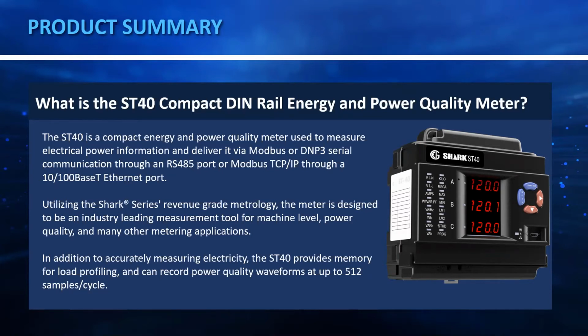This is especially important for factories or in universities where there are labs with very critical equipment. Sometimes what we see happening is that if there is bad power being fed into that critical equipment, it affects the efficiency of the equipment. Sometimes there are glitches on the equipment, and that causes downtime or loss of millions of dollars. So you really want to be able to get that granular sort of information, but also you don't have the space to put in a socket meter or a whole panel meter.